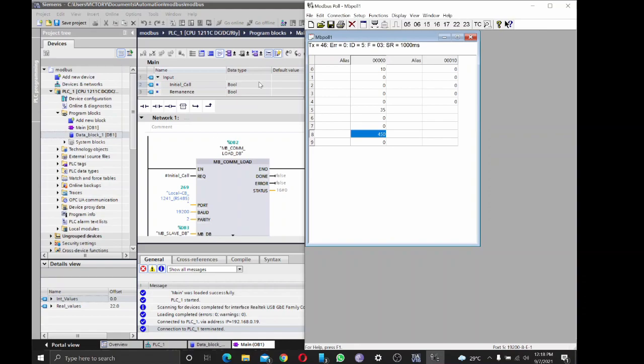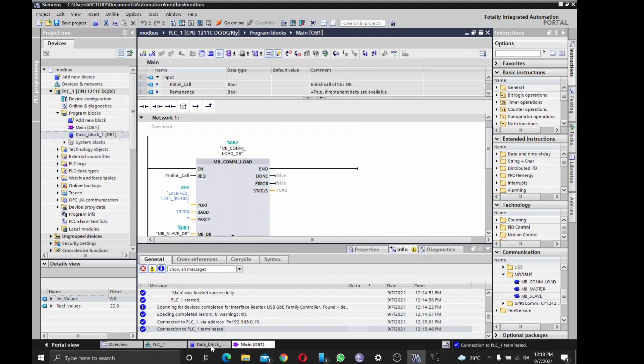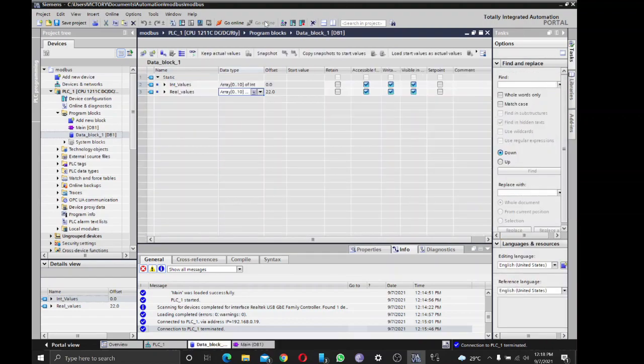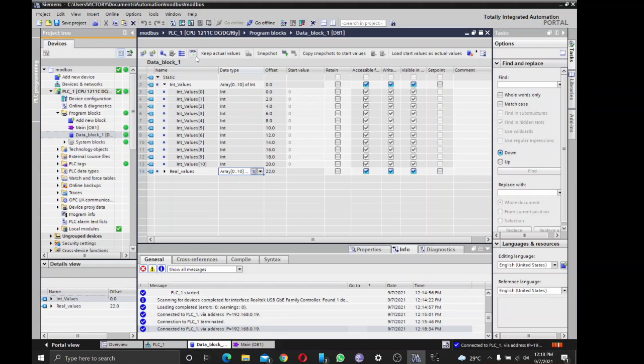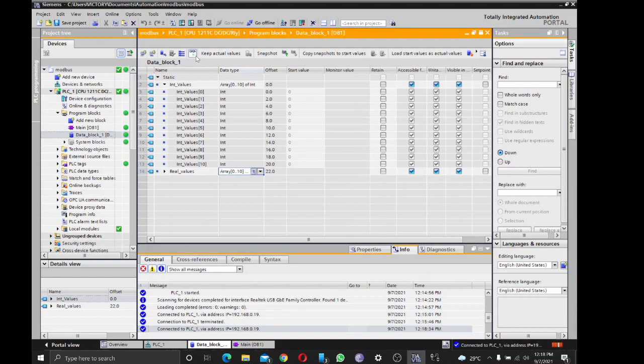So let's check our S7-1200. If these values - 10, 35, 450 - if they appear in the Siemens TIA Portal. So I have to go to data block, go online. Okay, so let's see and monitor. So good. What about values here? We have 10, we have 35, we have 450, which is sent from the Modbus Poll.